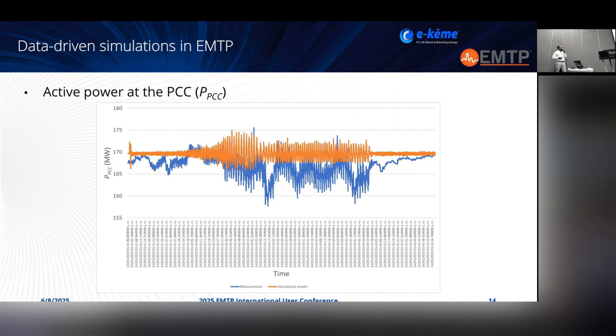From the perspective of the active power, we can see in blue the real, or measured, values at the wind farm. We can see the variable wind speed. The wind farm had a set point of approximately 170 megawatts, so we can see the variations of the wind speed. In simulation we didn't have this input variable, so we had to set the power to about 170 megawatts.